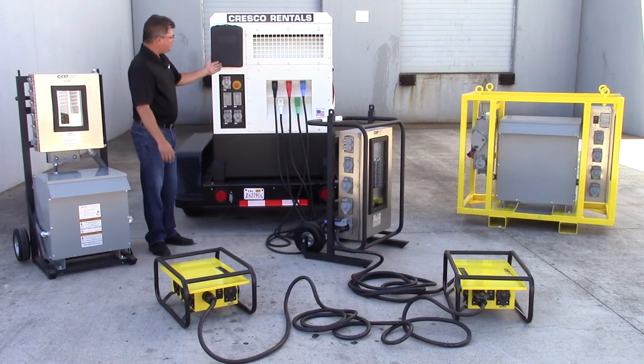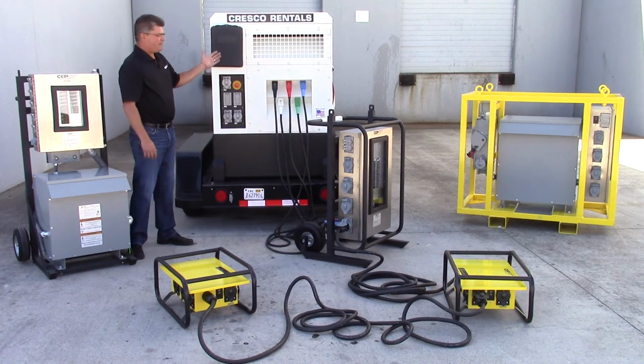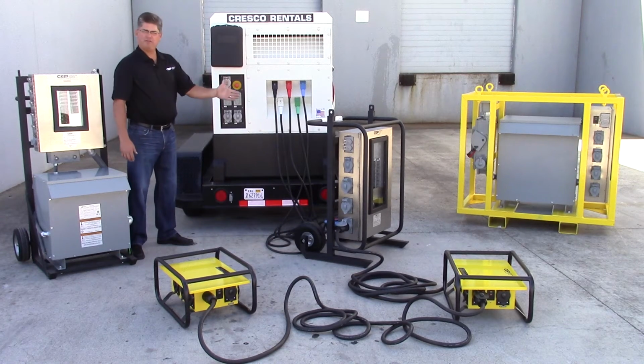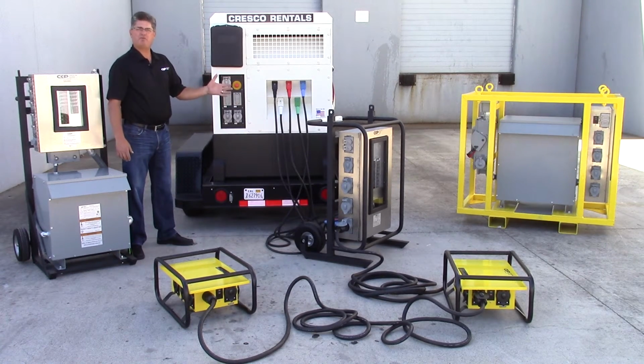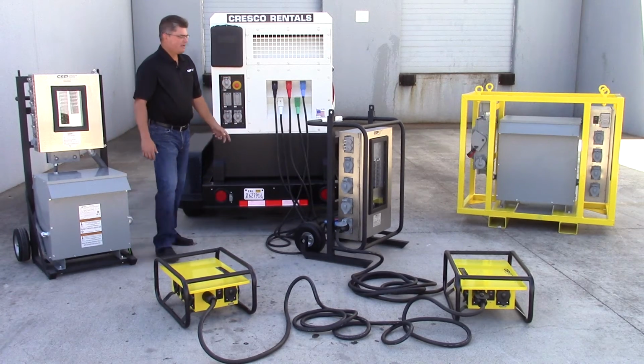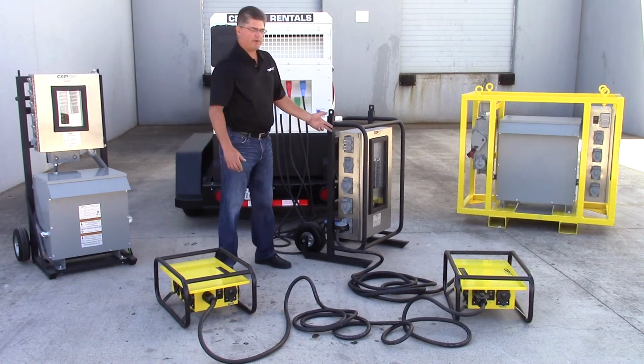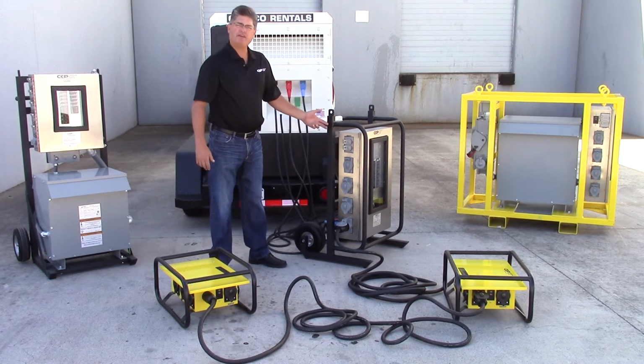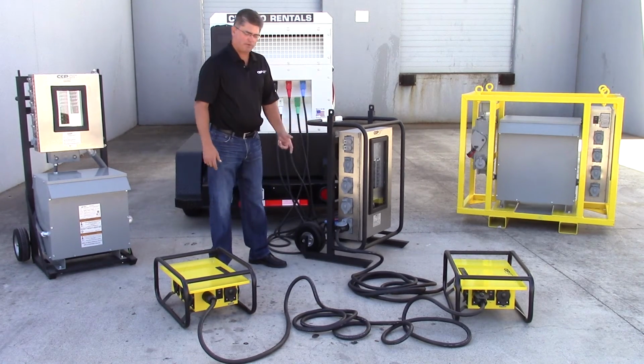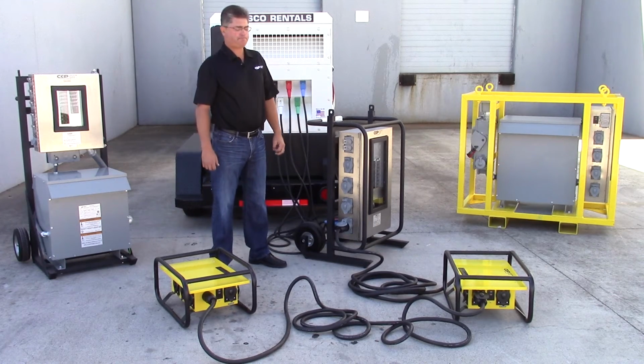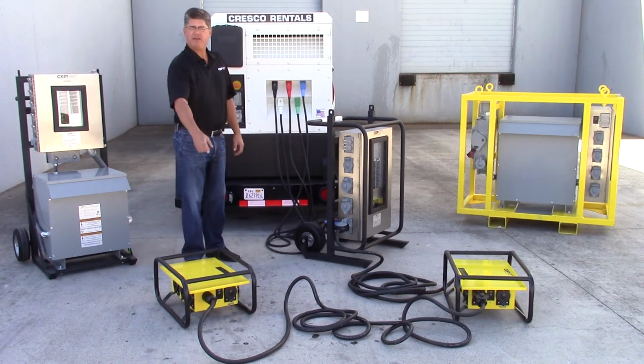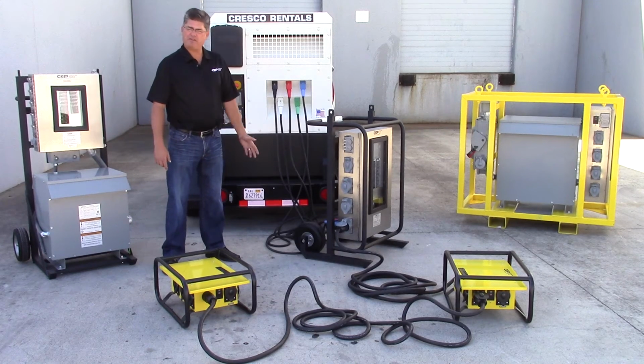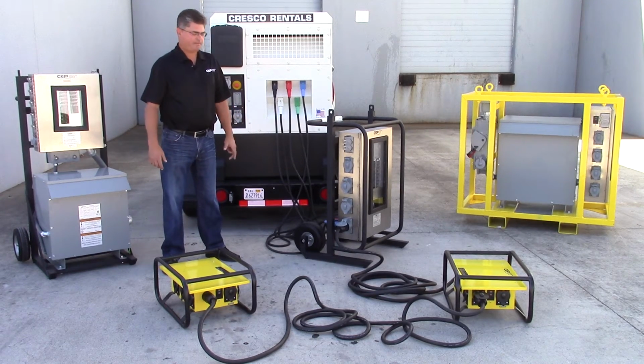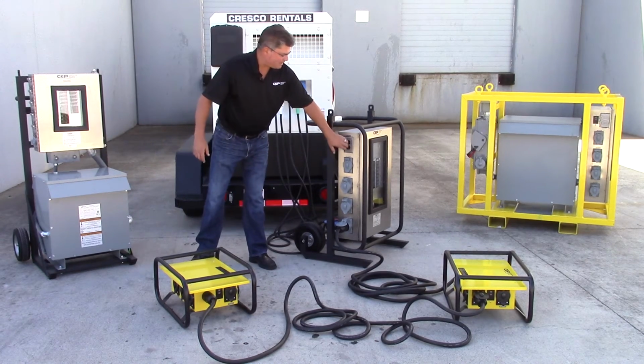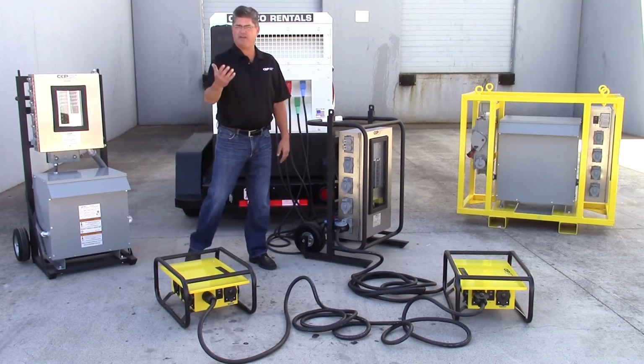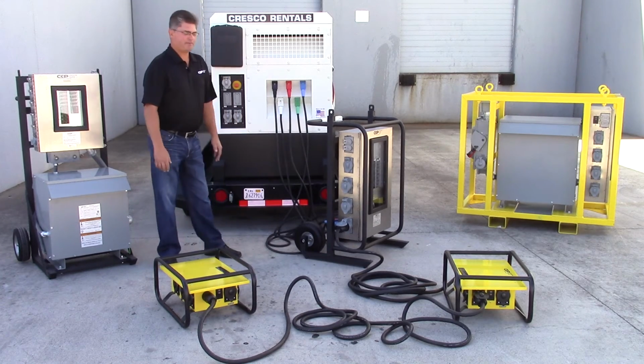With that, we have a 70 kW unit right here, which from an ampacity standpoint fits perfect with a 200 amp 120/208 volt 3-phase panel, which is what we have here. Now with this panel, we have 6 50 amp 120/240 volt receptacles, which allows the user to run 6 different spider box lines amongst the job. As you can see here, we've daisy chained two units in a row. However, you can go up to 3 units 300 feet from the power source. Further, we have a couple convenience outlets that allow the user to plug in battery chargers or anything of that nature right near the power source.